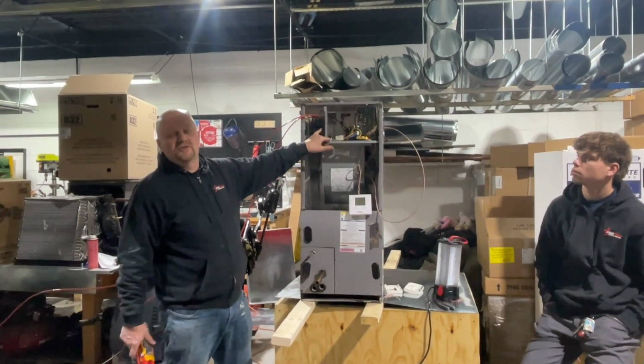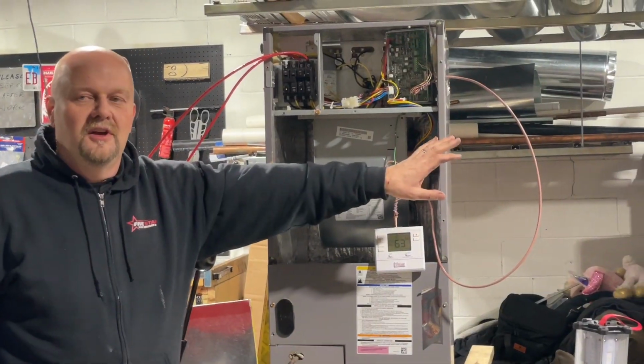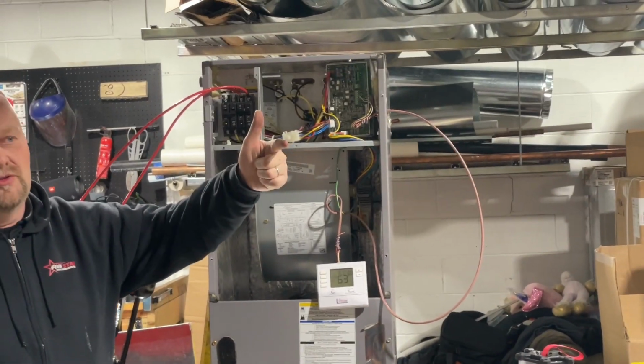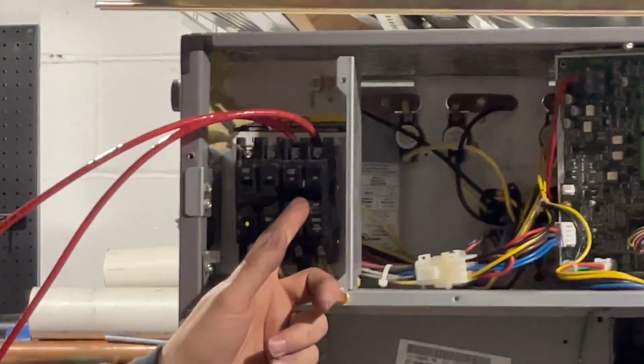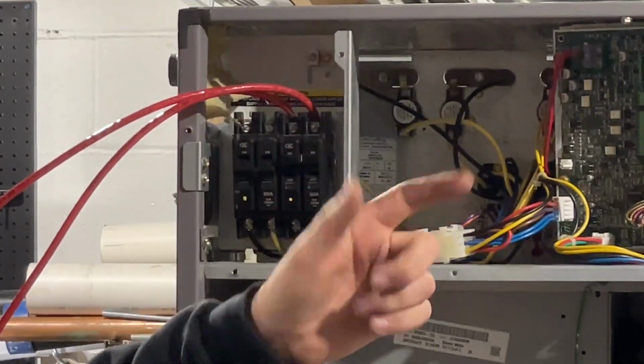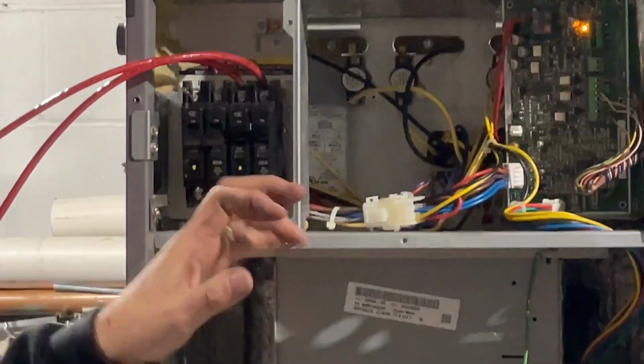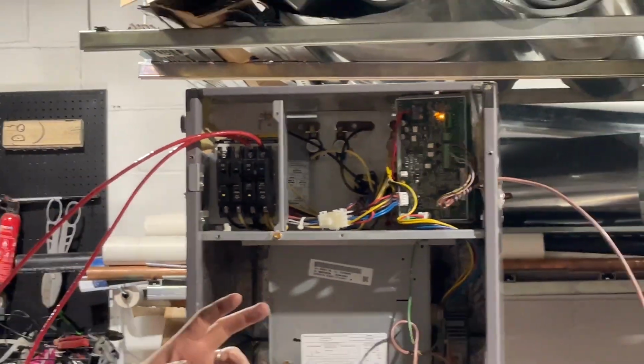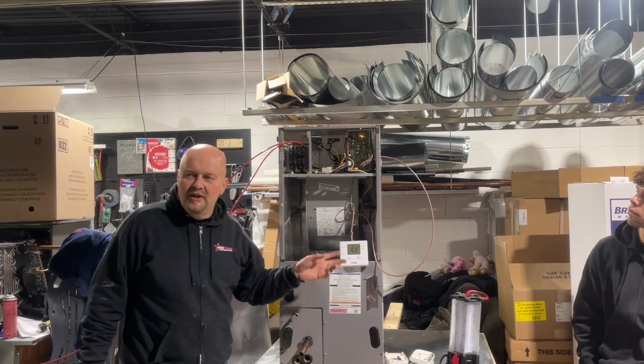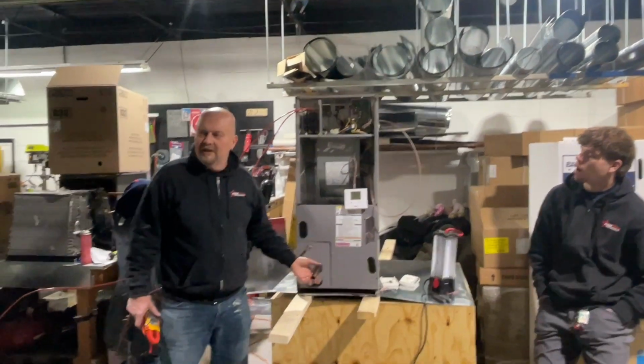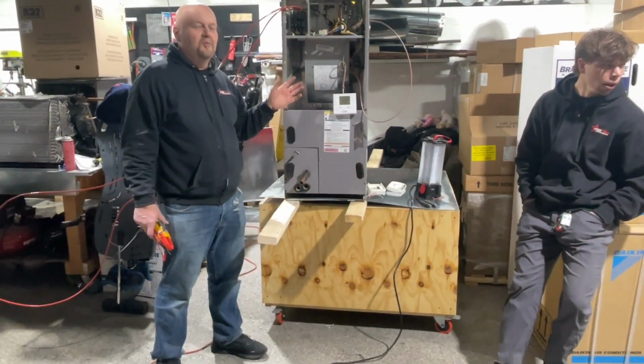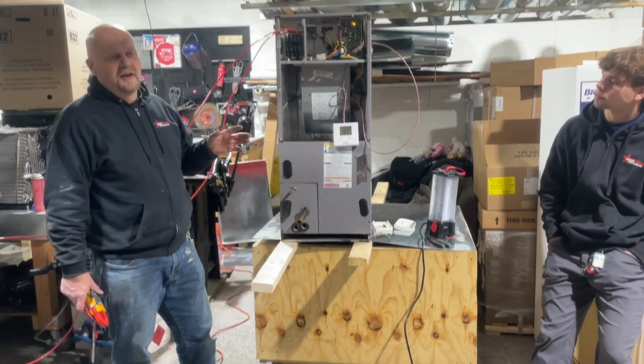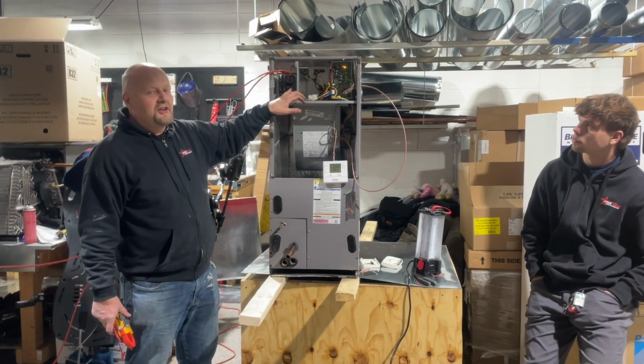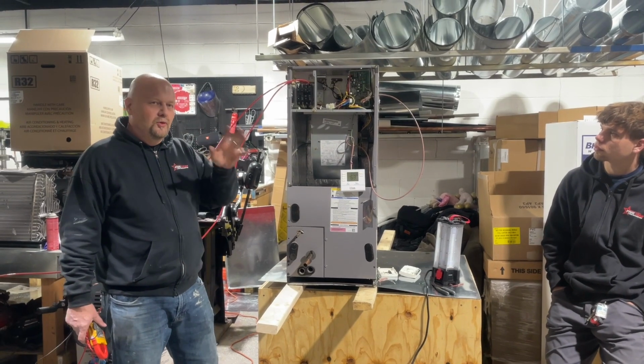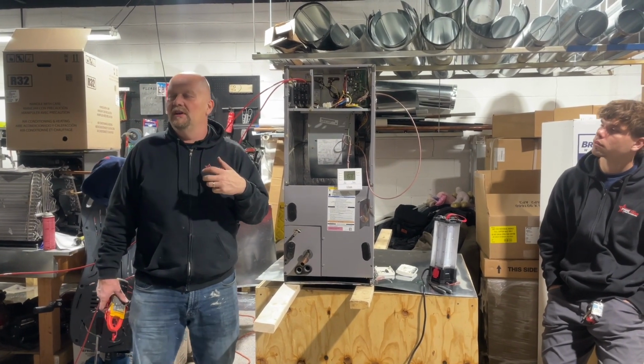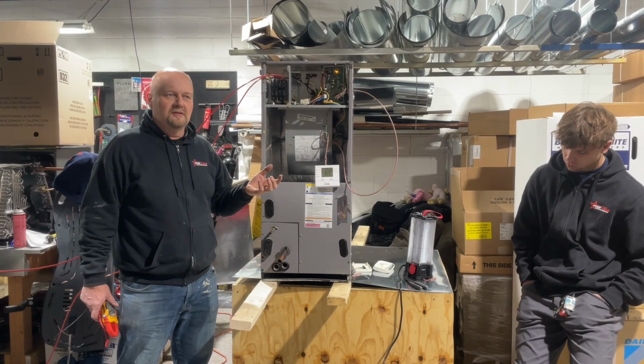So you decide as the installer who connects the low voltage end of it whether you're connecting it as W1, W2, W1 being the main circuit, and then W2 is the second stage, or if you want to use the second stage as E for emergency on a thermostat. Now this is not connected to a heat pump, obviously, but it could be, in which case the heat pump would be the primary source of heating, and then your electric heat would come into use in case the heat pump isn't capable of heating up, or in case it's in a defrost.